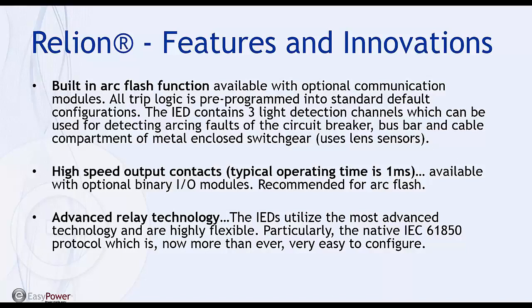Since speed is very important and you're losing a little bit of speed anyway, it's best to order this product with the high-speed output, which is just 1 millisecond. And when you get Relion, you get a lot of things other than the built-in arc flash feature. You get the advanced technology that we have in our switchgear now and our customers are using, mainly the easy to implement native IEC 61850 protocol and the flexibility of the relays. So there's a lot that you get when you use Relion relays. That's certainly a good solution for arc flash.